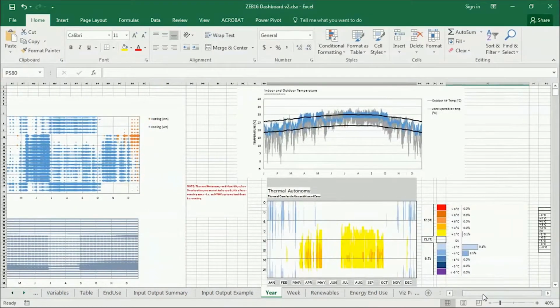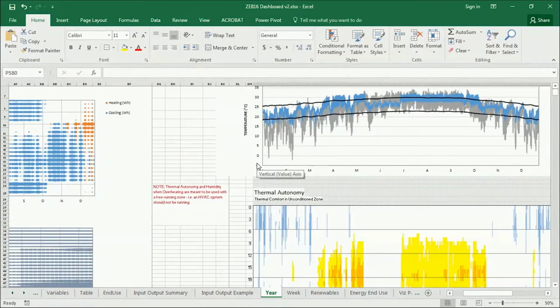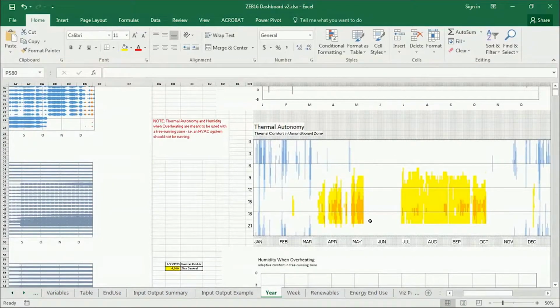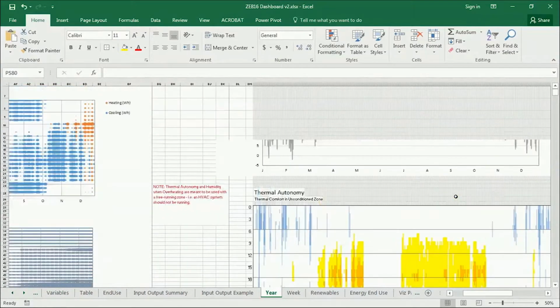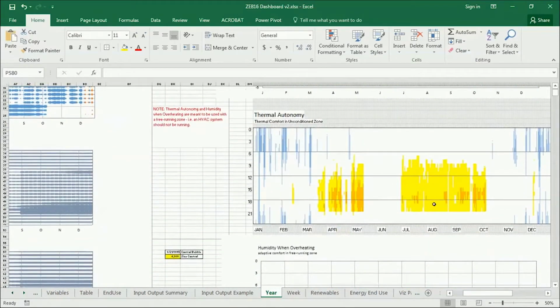So let's go over and see how it's actually working here. You can see that, well, first looking at the heat map, of course, when the HVAC systems are on, we're doing great. That's good. No surprise there. When there's no HVAC systems on, like here and here, it is a little warm, and actually we can see just how warm if we go up here. It's getting up into the high 20s, low 30s. That's pretty warm.